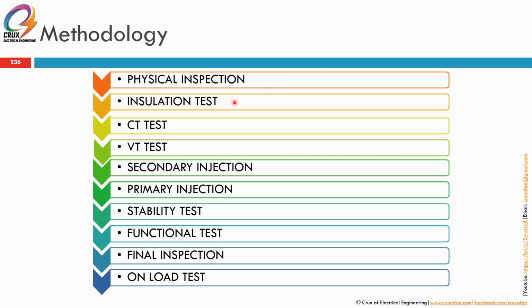The second part is the insulation test. The insulation test may consist of something as simple as the insulation resistance, followed by the polarization index, mostly for winding equipment, for motors and generators. And for high voltage machines, high voltage transformers and switchgear, we'll add further tests, such as AC hipot at 50 Hz, or VLF for cable, or tangent delta. So it depends on what kind of test the client has specified in the engineering specification.